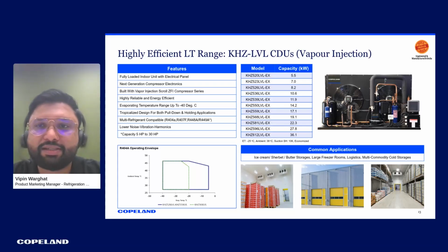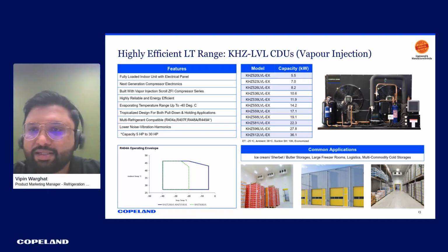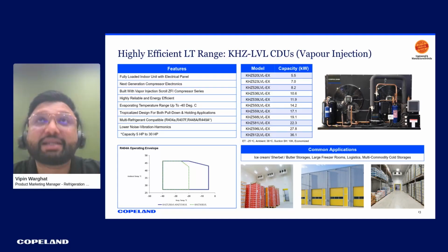Yeah, so this solution is available from 5 kilowatts to around 36 to 40 kilowatts of capacity for low temperature application. Of course, it has a fully built control electrical panel and a lot of refrigeration controls. It can handle temperatures as low as minus 40 degrees Celsius, which is quite useful for low temperature application. And the unit is designed in such a way that it can handle the Indian conditions. So definitely it can work at higher ambient temperatures as well, and it can handle multiple refrigerants as well.